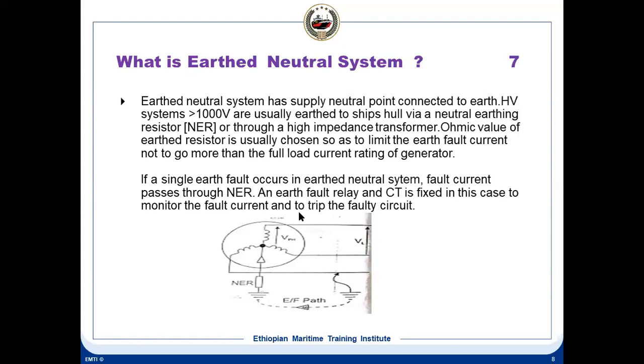And the ohmic value of this resistor is so chosen as to limit the earth fault current so that it does not go more than the full load current rating of the generator. That is one criterion in selecting this NER, the current limitation. It should not be more than the full load current rating of the one generator.